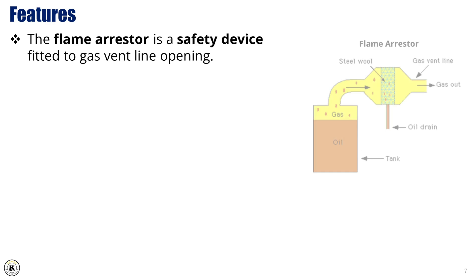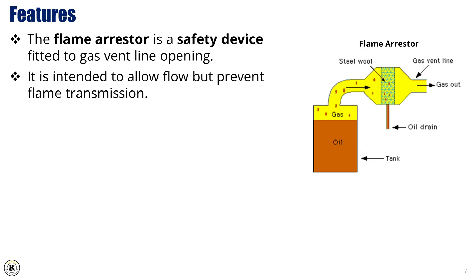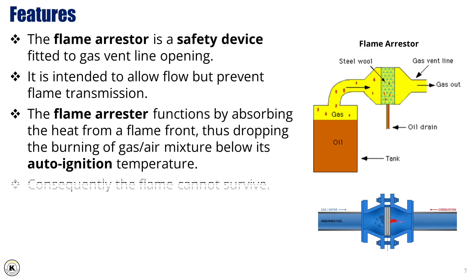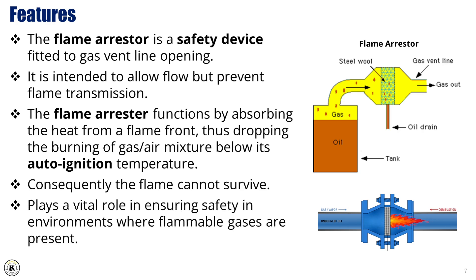The flame arrester is a critical safety device fitted to the gas vent line opening. Its main purpose is to allow the flow of gas while at the same time preventing flame transmission, which could pose a serious hazard. The flame arrester functions by absorbing the heat from a flame front, dropping the temperature of the burning gas-air mixture below its auto-ignition temperature. Consequently, the flame cannot survive, and the system remains protected from the risk of backfire or explosion.